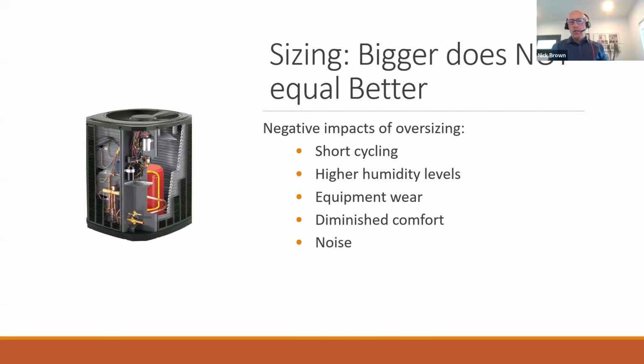Another question on sizing. Isn't oversizing a major impediment of heat pump efficiency? Or Bobby, would you say it's an impediment of heat pump and gas furnace split system efficiency? Yeah, it's just back to this last slide. I think, yeah, efficiency, you're going to overcycle. So if you put a 2-ton unit where a 1-ton unit should be, it's never going to find its happy spot. And that's what an inverter wants to do, if it's sized correctly. I've seen units run at 5 amps in 95 degree weather, because it's sized correctly. It finds its happy spot. The condensing unit ramps down, and it's much more efficient. So does it impede efficiency? 100%, yes.